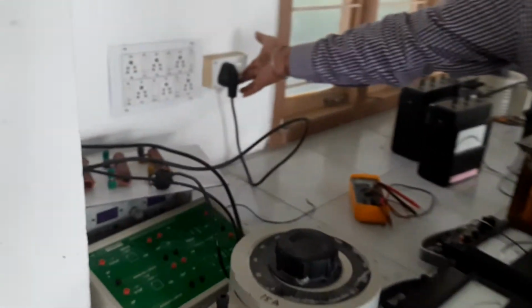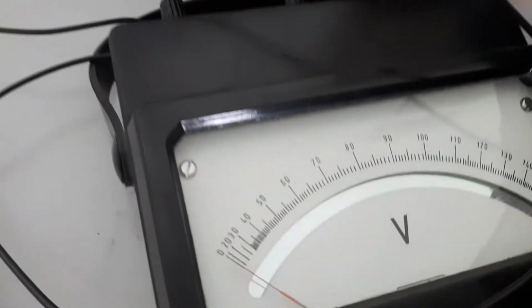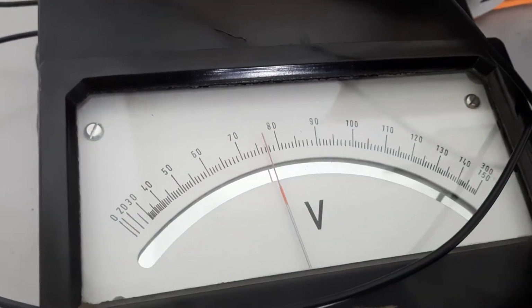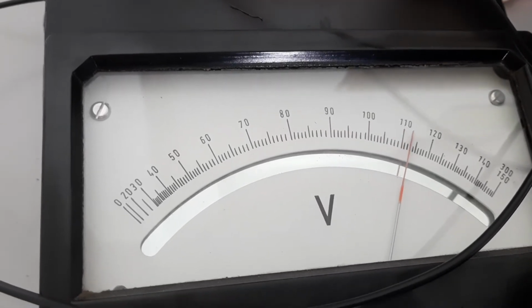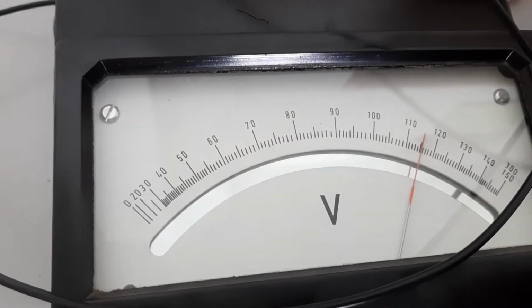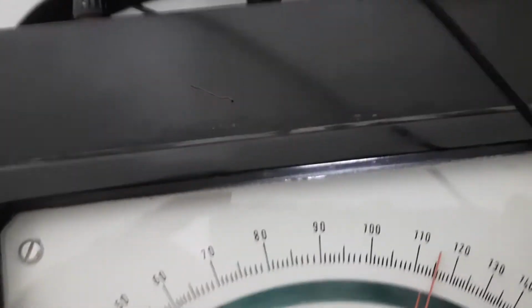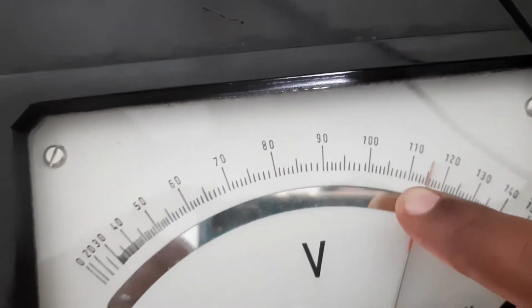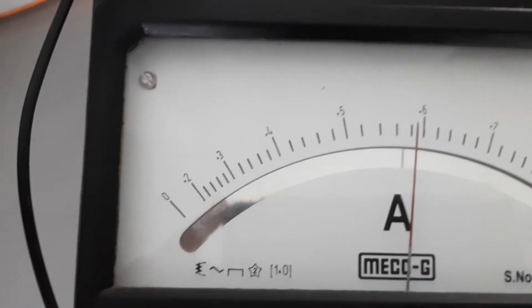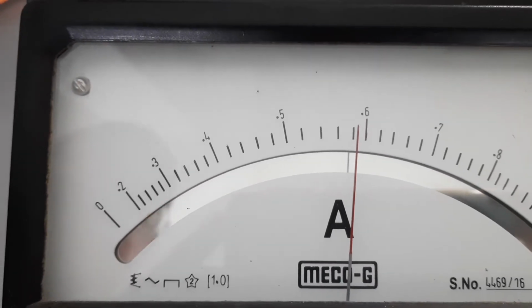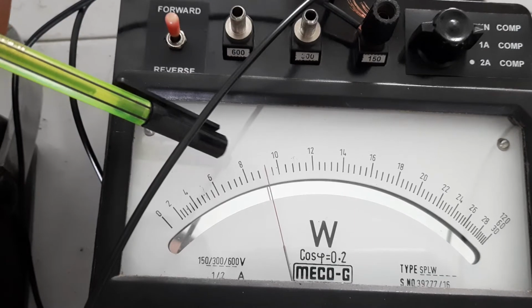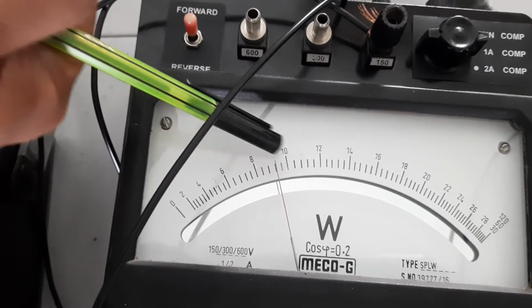I am switching on the single phase variac. By rotating this single phase variac, I am applying the voltage until 115 volts. You can see 115 is to be achieved. Always remember, when you are seeing from the top, the mirror and the needle must coincide, so that there is no parallax error. Whatever reading we get, we have to note it down. Here the voltage applied is 115 volts, and the current reading is correctly 0.58, and the wattmeter reading is about 9, 9.4 or 9.5 like that.